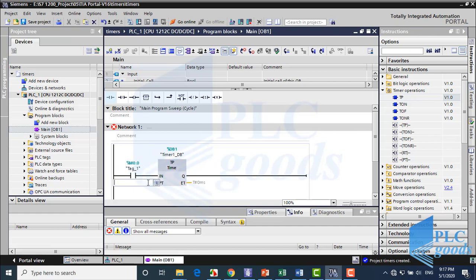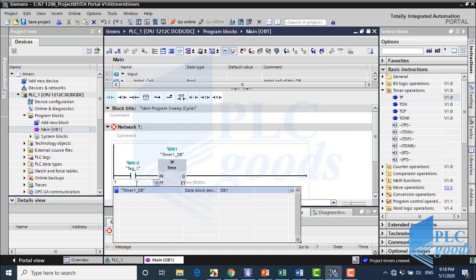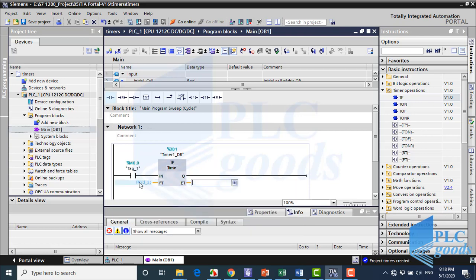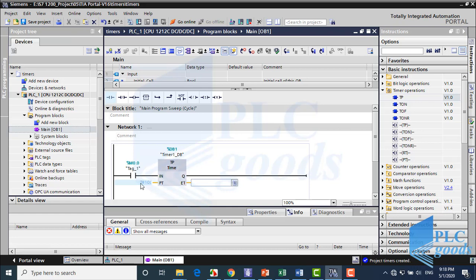At the second input we need time. The format of time is T letter plus sharp sign plus time and its unit. Here, if you forgot to write T letter and the sharp sign, TIA adds them to your time automatically.